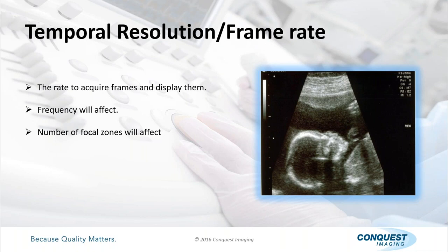You'll see it in the description, either here or over here, it'll say FR, which stands for frame rate. But a lot of people, because it says hertz after it, say it's frequency, because FR sets you up for frequency, right? And it kind of is. It's the frequency at which the screen, or the image area, is refreshed, but it's not the frequency of the probe. And that's the caveat I want to make sure everybody understands.